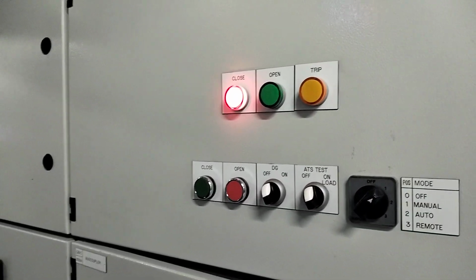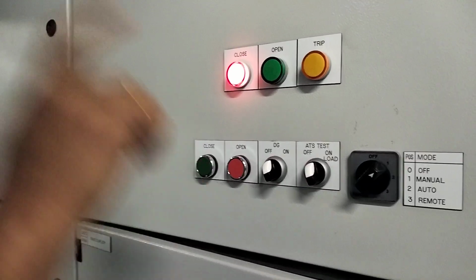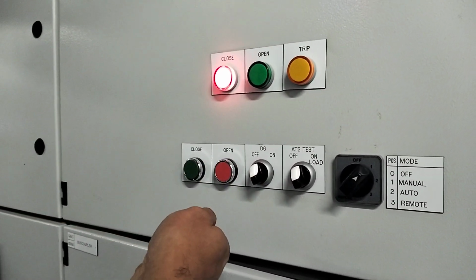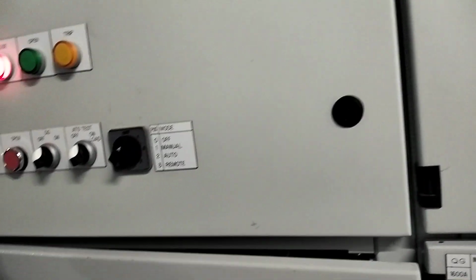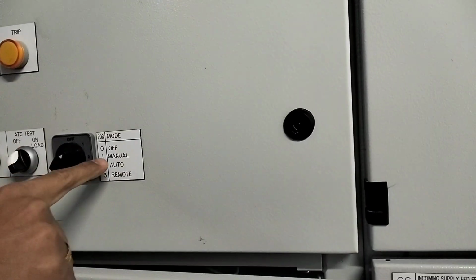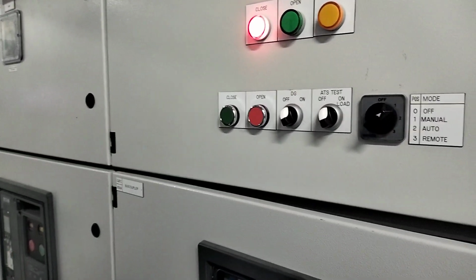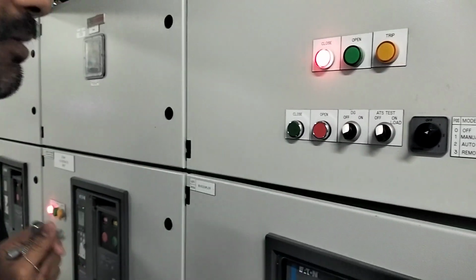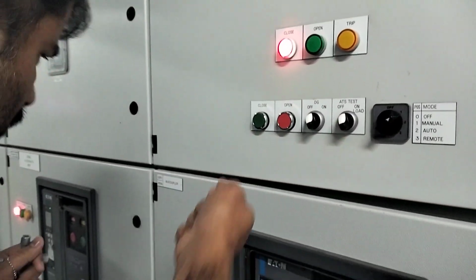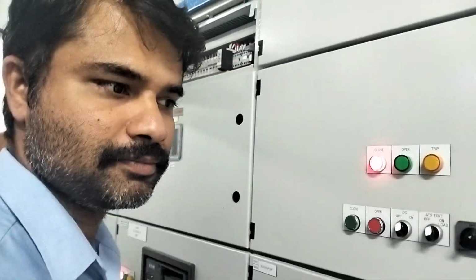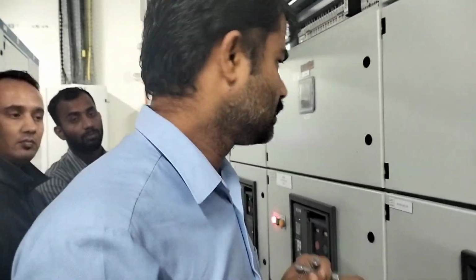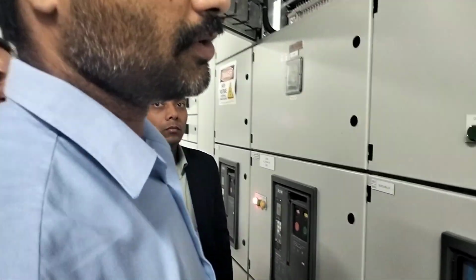If you want power immediately and want to run the generator, just turn it on. Right now I can start the generator because it's manual. You can start, but nothing will happen. The voltage will just be here. If you want to run like this, keep it in manual and run the generator. To be safe before I do the changeover, I make sure the voltage has reached. You can check the voltage on the voltmeter here. Then the voltage is healthy.